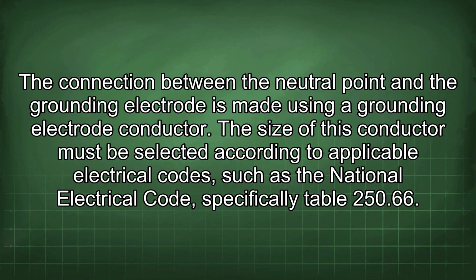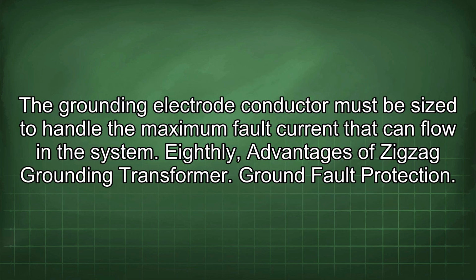The connection between the neutral point and the grounding electrode is made using a grounding electrode conductor. The size of this conductor must be selected according to applicable electrical codes, such as the National Electrical Code, specifically Table 250.66. The grounding electrode conductor must be sized to handle the maximum fault current that can flow in the system.